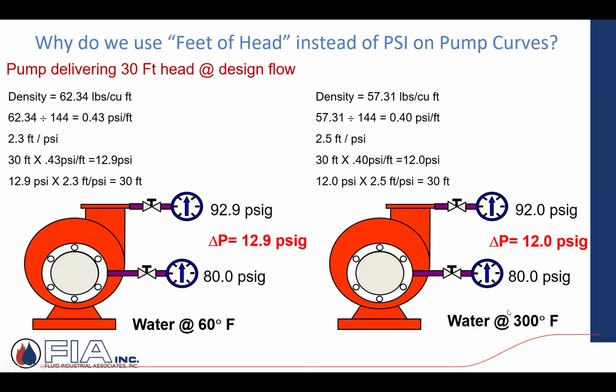When I suddenly am pumping 300-degree water, which is not the norm, but you might have an application where you're pumping 300-degree water, well, I know the specific gravity, or the density, is different than at 60 degrees. In this case it's 57.31. When I divide that by the 144 square inches, I have a number of not 0.43 but 0.4. So when I have that 30 feet times 0.4, I'm going to read a 12-pound differential across the gauge. Still moving 30 feet of head, still developing 30 feet of head, but it's going to read differently on the gauges because the weight of that water is different. I'm dealing with 300-degree water, and the density is different than at 60 degrees.